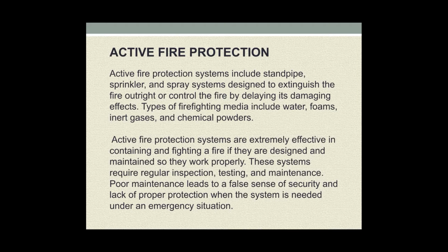Active fire protection systems are extremely effective in containing and fighting a fire if they are designed and maintained so they work properly. These systems require regular inspection, testing, and maintenance. Poor maintenance leads to a false sense of security and lack of proper protection when the system is needed under an emergency situation.